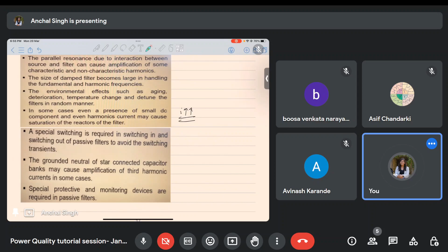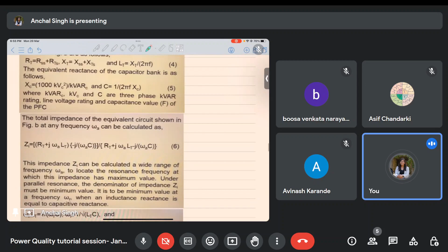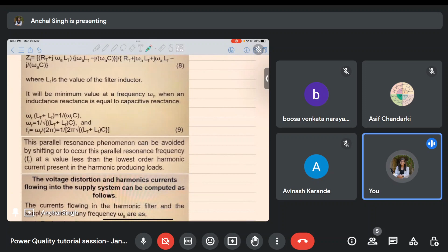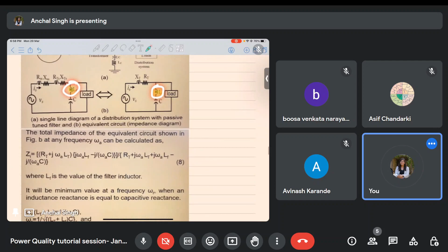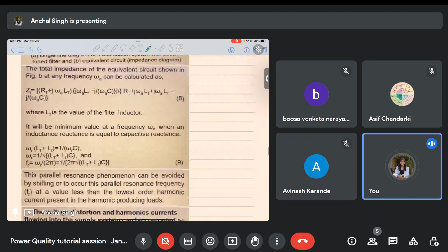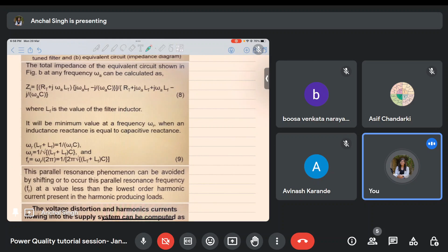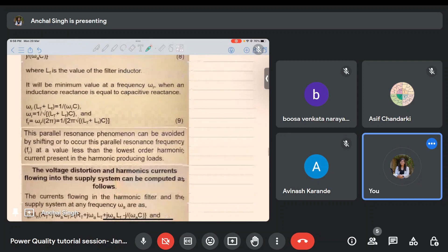Okay. So we have discussed the parallel resonance problem in these filters. Now there are ways to mitigate those problems. Why does resonance occur? Because of this source inductor and this filter capacitor. Because of the presence of this equipment, the parallel resonance is occurring in the system. Now, if we do the mathematical analysis of the system, then we find one solution where we put an inductor in series with this capacitor. And when we again do the mathematical analysis, we will observe that using the variable filter inductor L_F that we had just put here, we can change the resonance frequency of our system according to our need. Initially, it was system dependent, but now using the filter L_F, we are able to change that resonance frequency, and we'll make sure that this resonance frequency does not coincide with any of the harmonic components of my load current. Okay.